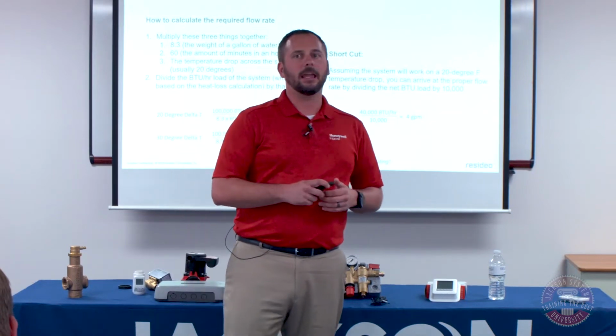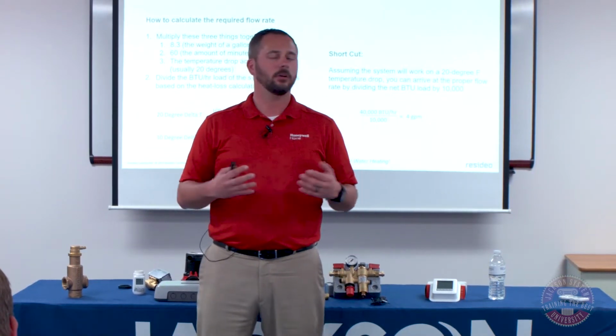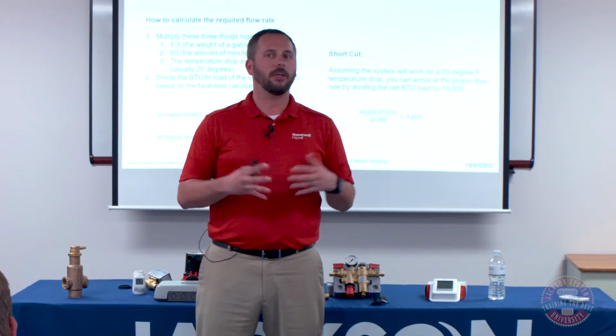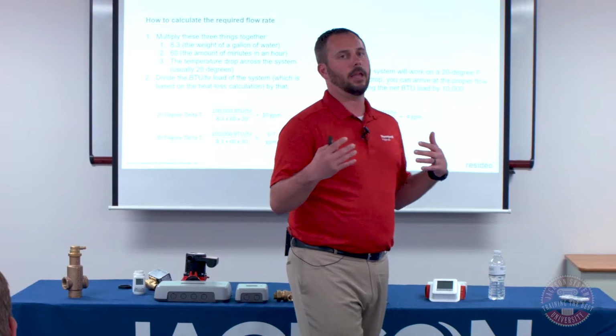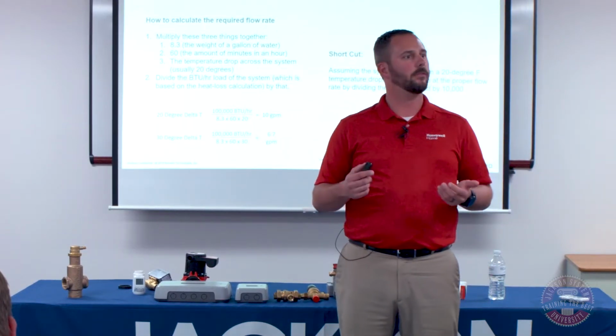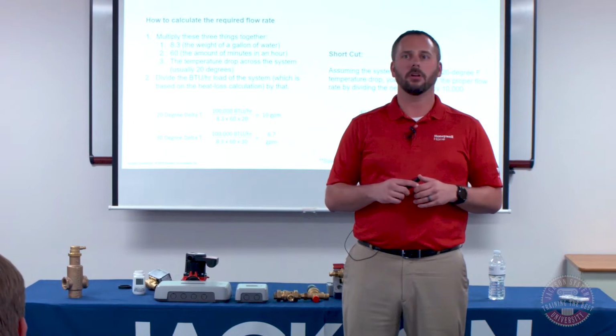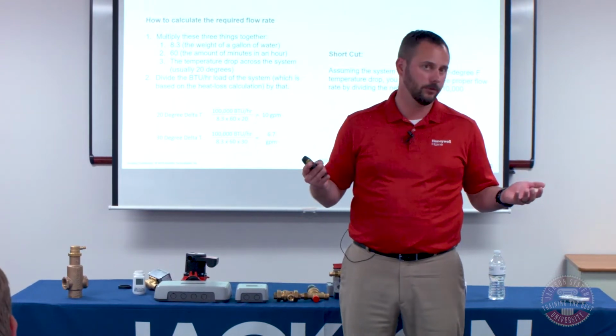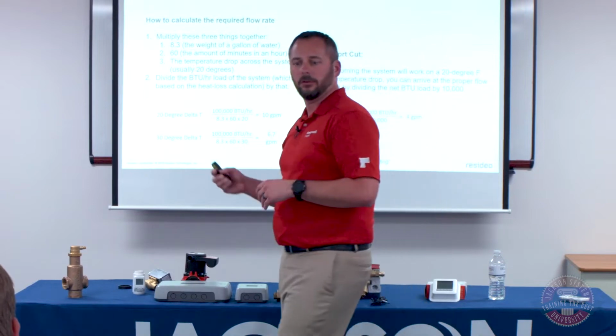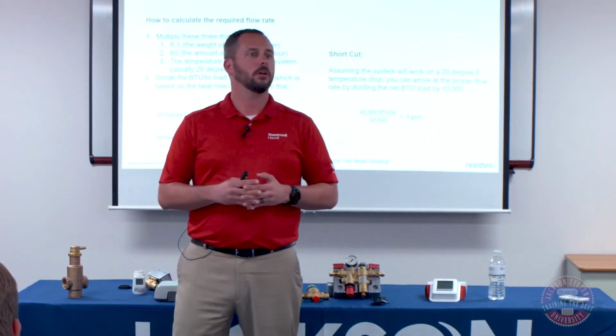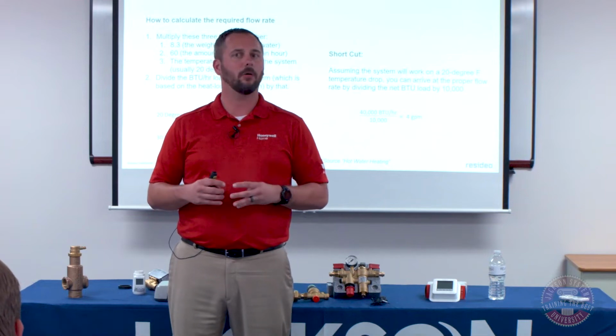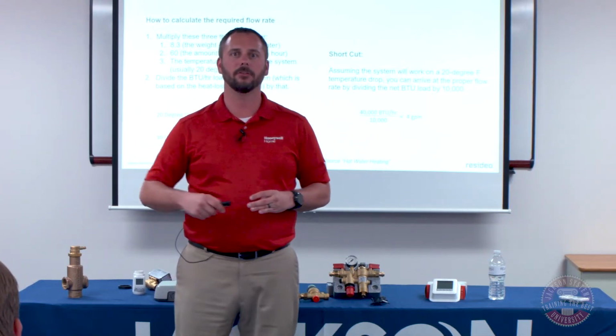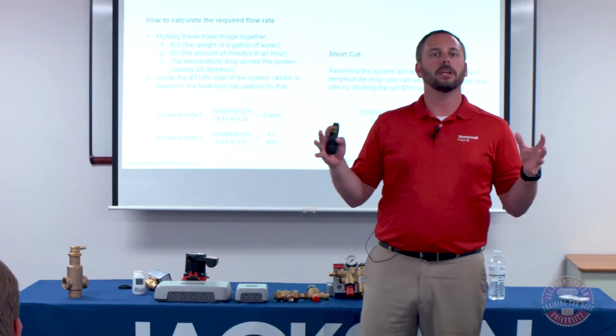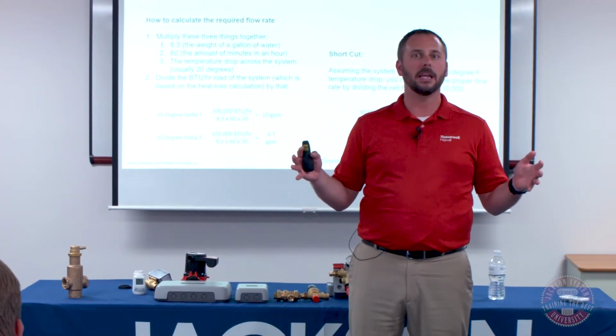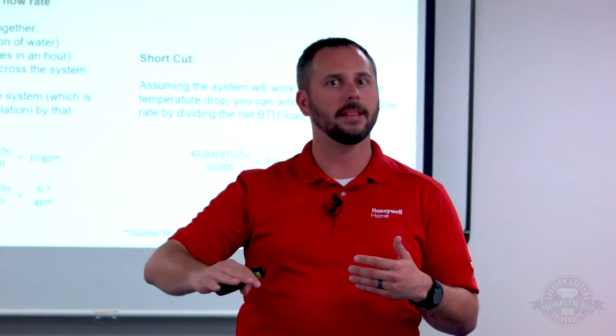So let's say we've got a zone pump that's feeding an area that's, I don't know, let's say 1,000 square feet. Every market's going to be different, every house is a little different, but if you did a rough heat loss calculation, let's just say on average it's going to need 20 BTUs per square foot, relatively new construction. So 1,000 times 20, you're going to have 20,000 BTUs. Divide that by 10,000, that pump needs 2 gallons per minute. And I don't have that math up there, I just did that one off the cuff. But you can basically get a rough idea for how big the space is that's being heated with that zone pump, and just divide that by 10,000, and there's your flow rate.